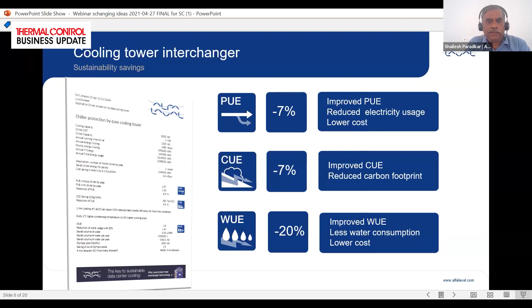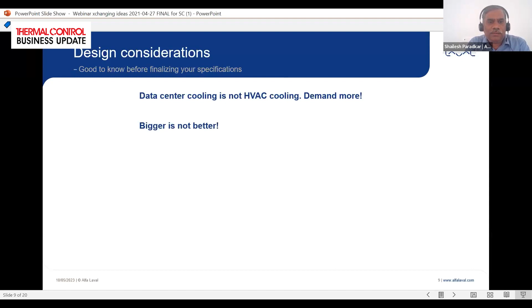When it comes to the data center, most of us know HVAC, and they try to compare. It's basically the same space cooling, but it's not. A data center is a much more demanding application, and for that, proper design considerations need to be adopted. One of the myths is that you can provide bigger heat exchangers that can take care of some inefficiencies and probably the extra capacity required during certain times, but it's not the case.